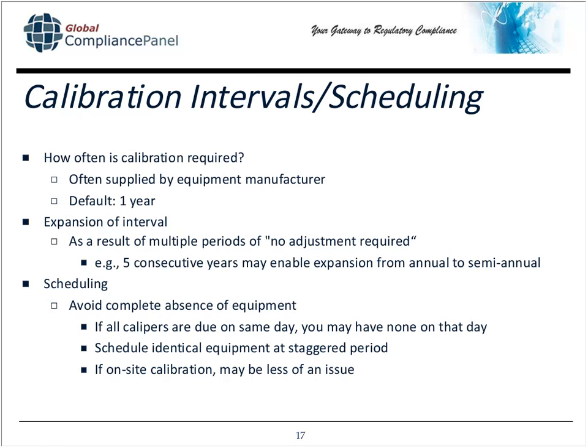An interesting question when it comes to determining calibration intervals or scheduling is how often is calibration required on a particular piece of equipment? Much of the time this is supplied by the equipment manufacturer. Usually the default is about a year. That's usually where most people start, especially if the calibration interval is not specified by the equipment manufacturer. But it's okay to then further expand your interval. For example, if you calibrate a particular piece of equipment once a year for 5 consecutive years, and you have 5 consecutive years of no adjustment required, which means that it's always been in spec, it was never out of spec.